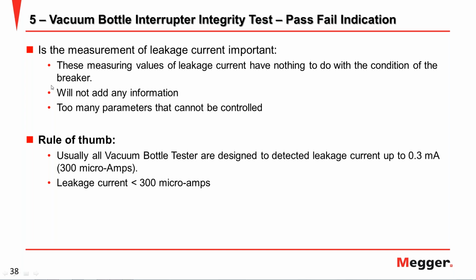It is very much impacted by many things. Too many things can influence the leakage current, so we cannot use it for trending. For example, if you got 100 microamp, suddenly it can change to 600, or maybe more than 300 microamp. This is why we cannot use the leakage current value on the vacuum bottle test as a reference.